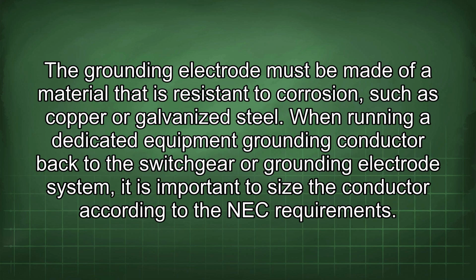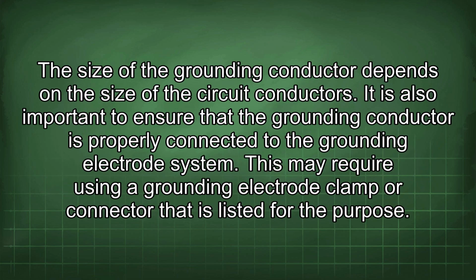When running a dedicated equipment grounding conductor back to the switchgear or grounding electrode system, it is important to size the conductor according to the NEC requirements. The size of the grounding conductor depends on the size of the circuit conductors. It is also important to ensure that the grounding conductor is properly connected to the grounding electrode system. This may require using a grounding electrode clamp or connector that is listed for the purpose.